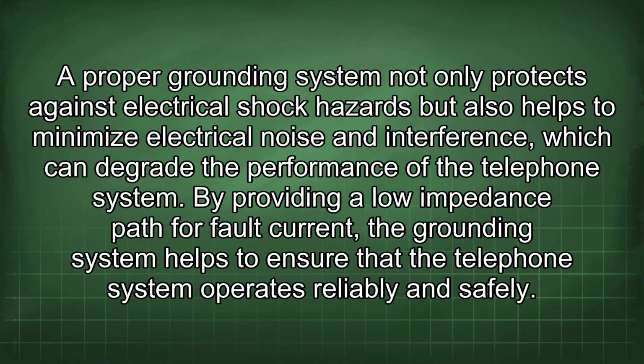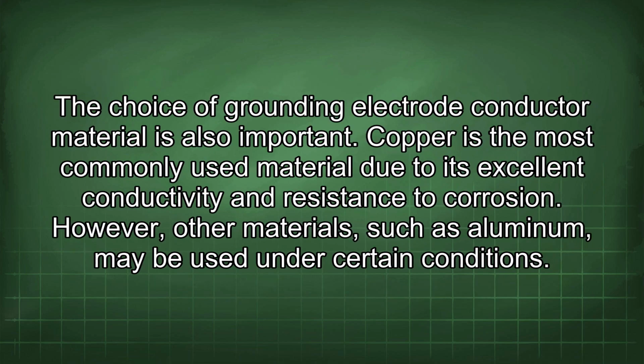A proper grounding system not only protects against electrical shock hazards, but also helps to minimize electrical noise and interference, which can degrade the performance of the telephone system. By providing a low impedance path for fault current, the grounding system helps to ensure that the telephone system operates reliably and safely. Choice of grounding electrode conductor material is also important.